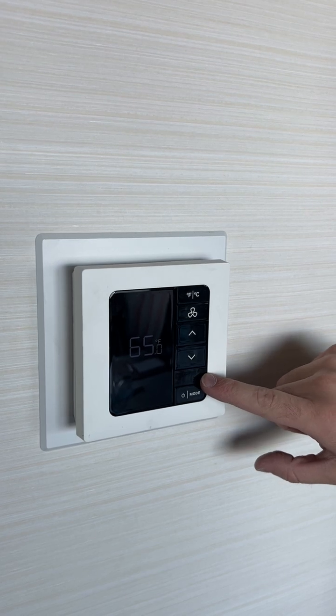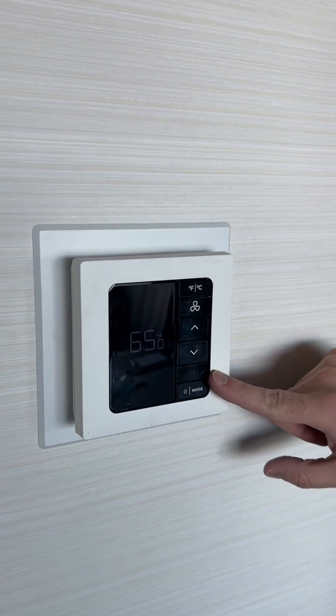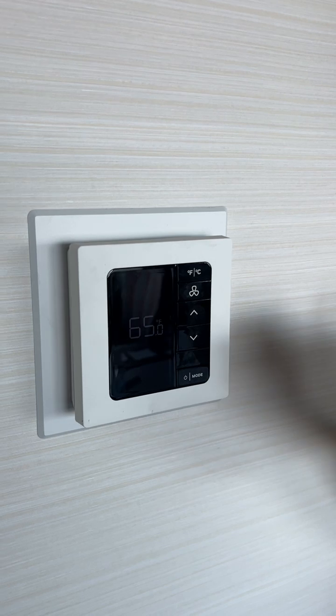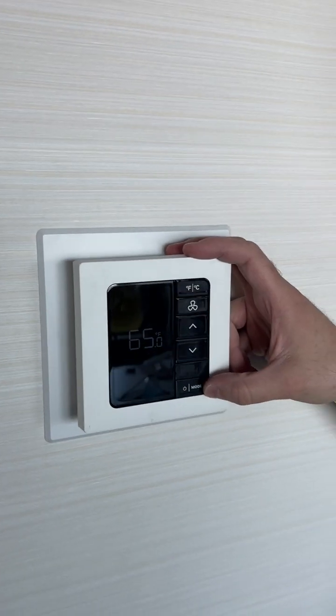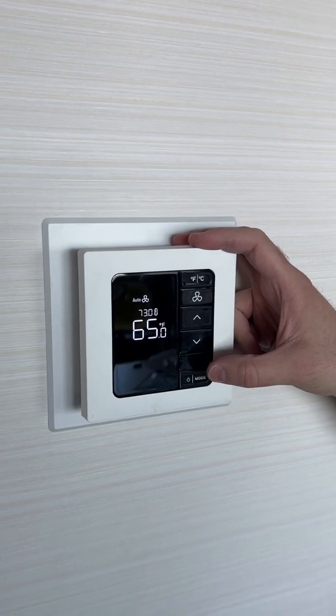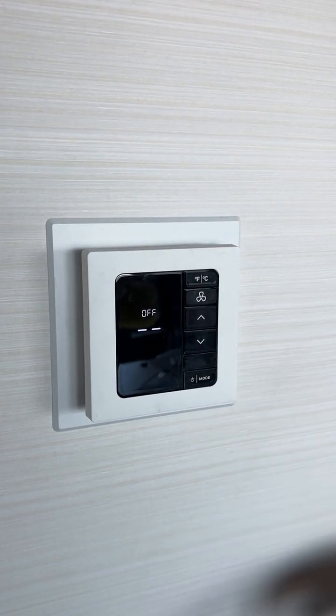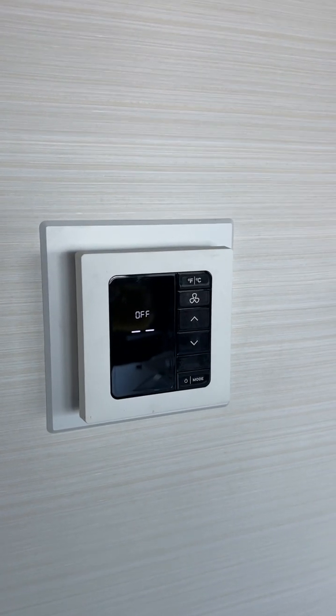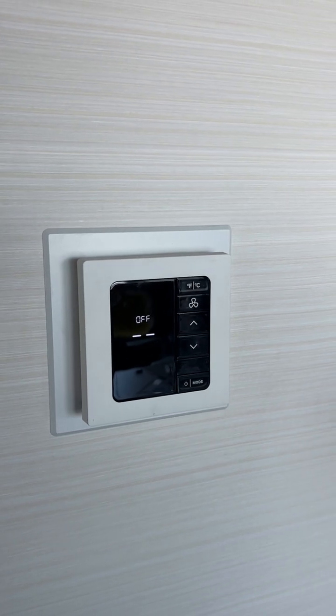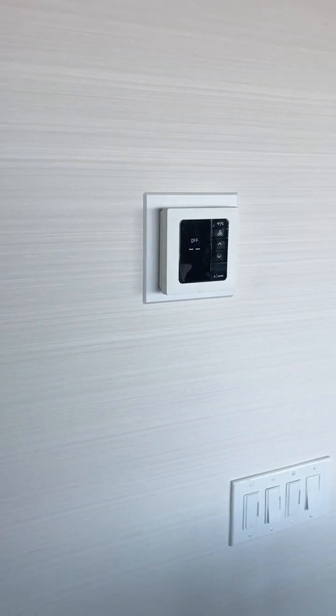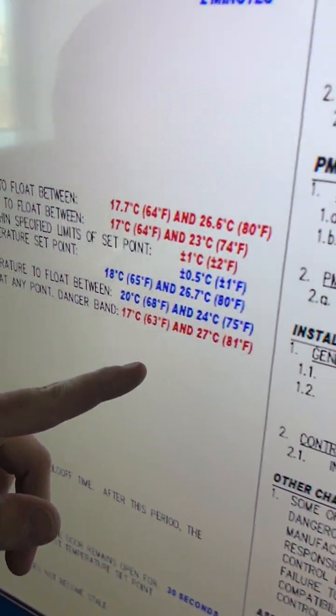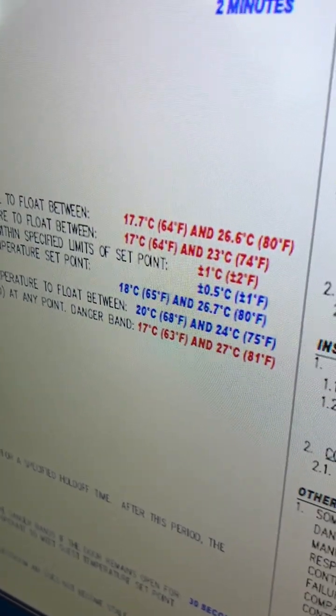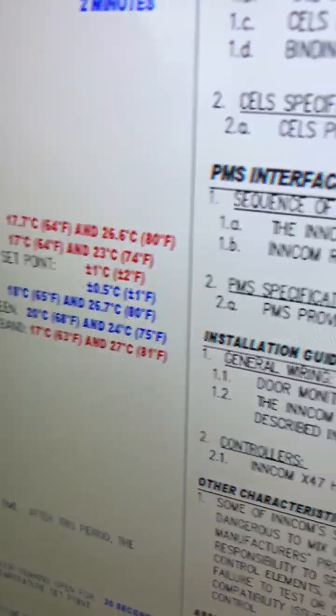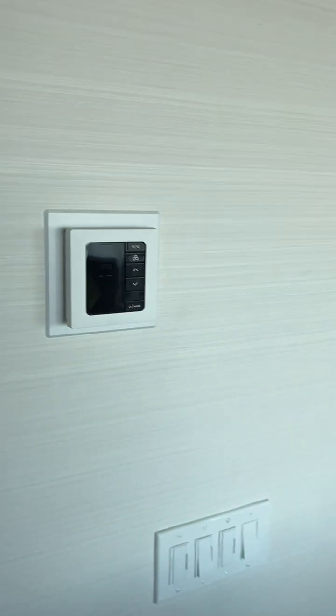We have a motion detector right here. So onboard motion handles the motion only timeout, which I'll talk about in a little bit. Then mode, we have off and we have automatic. If you press off, it's not a true off. It's an emergency band, which for you guys is 63 to 81. So if the room gets colder than 63, it'll kick in heat, and above 81, it'll kick in cooling, even if it is displaying off.